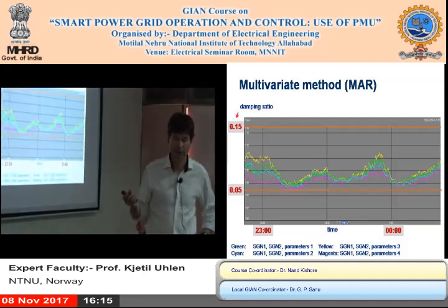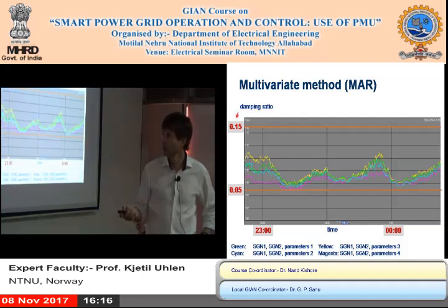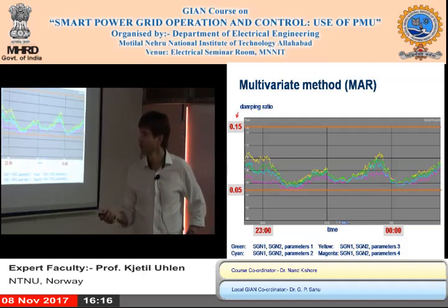They have made their PhDs on that subject and have found quite reliable methods to monitor the damping of this mode in real time. You see that it varies here from 10% down to 5% over some hours.